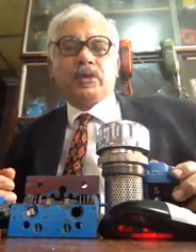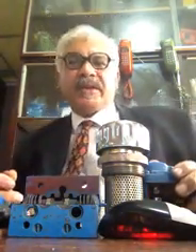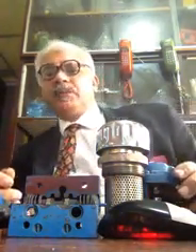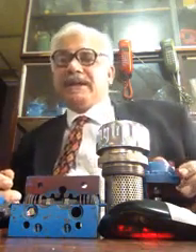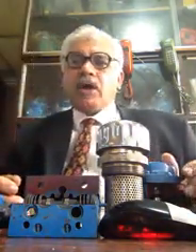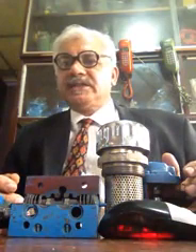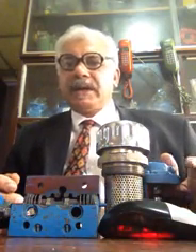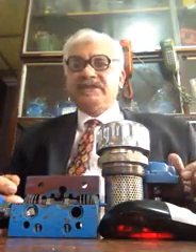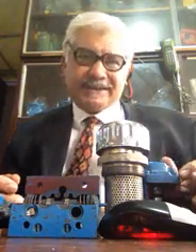Efficiency: the ratio of output to input is called efficiency. Volumetric efficiency of a pump is the actual output in GPM divided by the theoretical or design output. The overall efficiency of a hydraulic system is the output power divided by the input power. Efficiency is usually expressed as a percent.